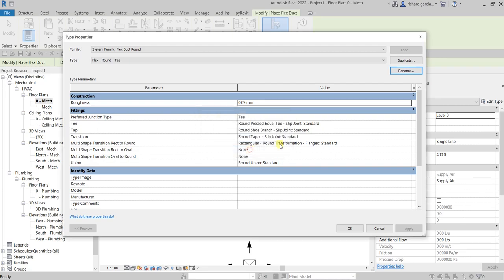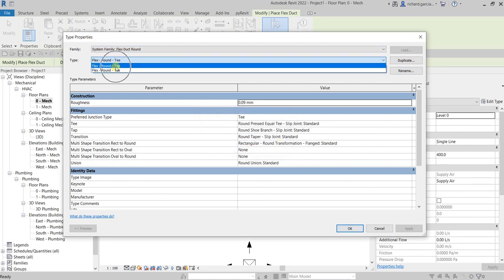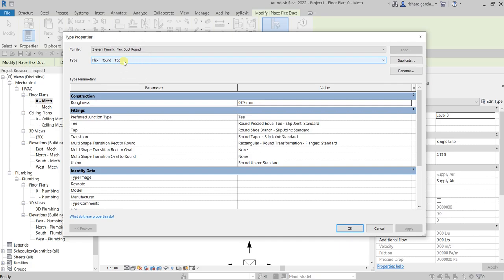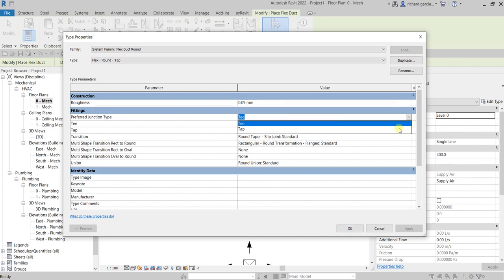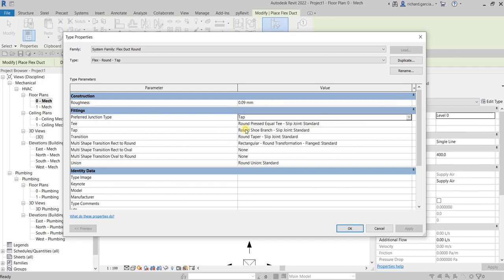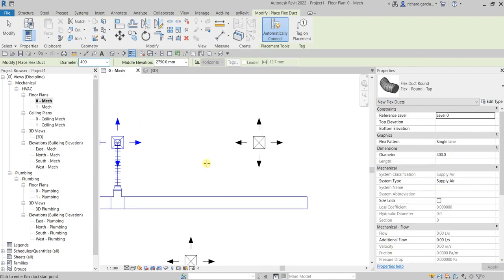By the way, you can also rename the other one to 'Tee' since its junction type is Tee. Now go to the Tap type and under the Fittings parameter, look for the Preferred Junction Type. As you can see it is currently set to Tee — just change that to Tap, then select OK. You are now ready to create your duct with a tap connection.